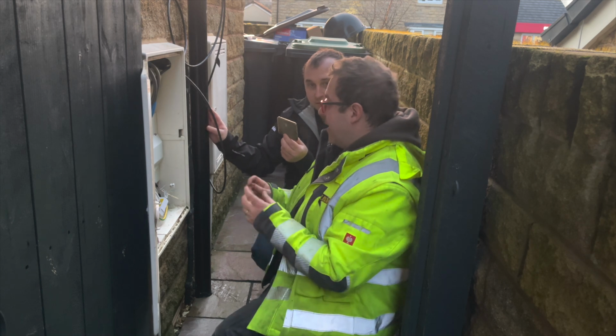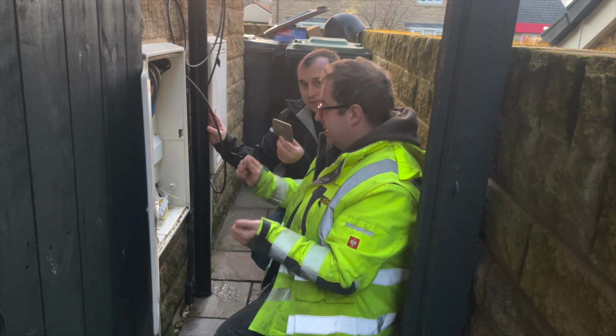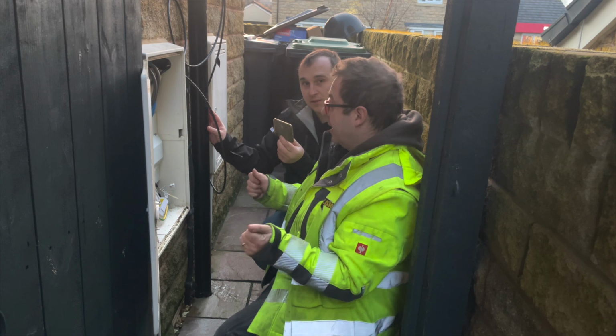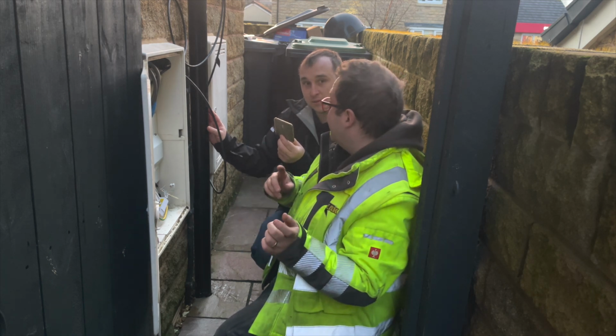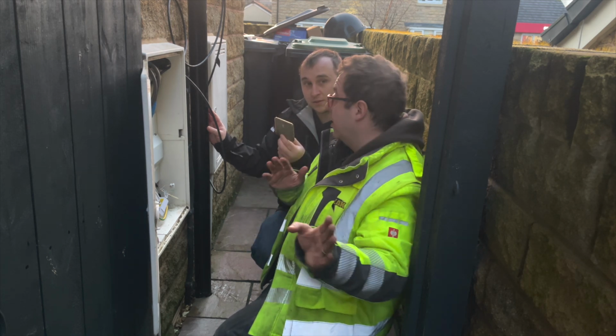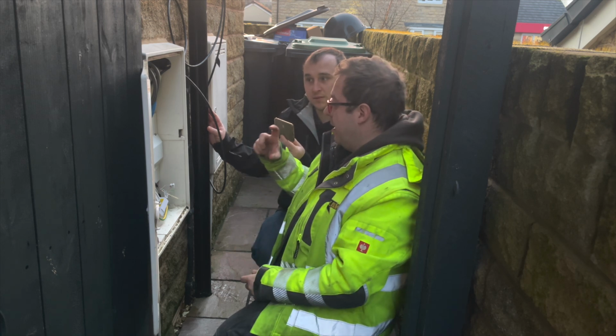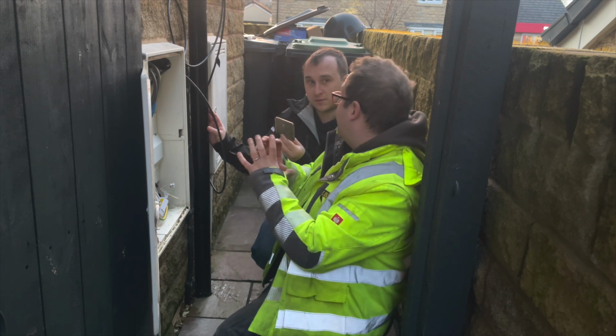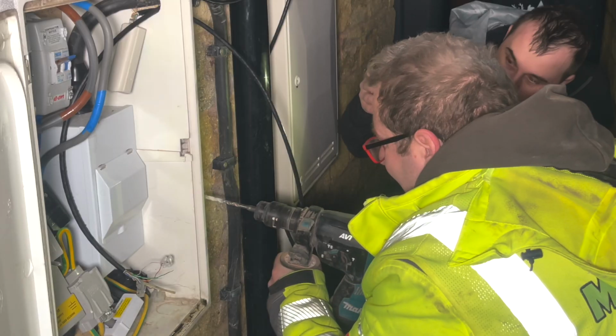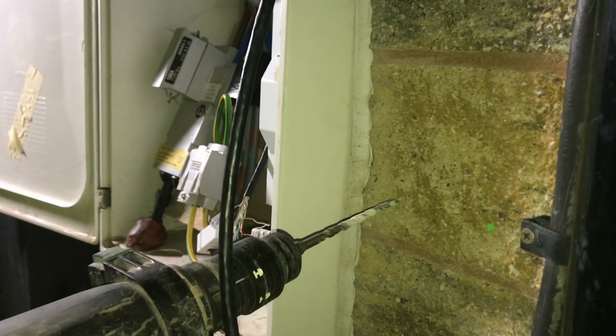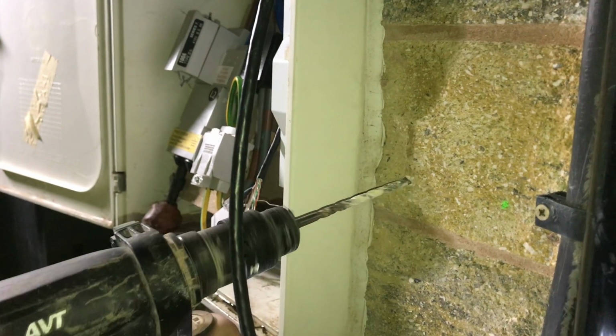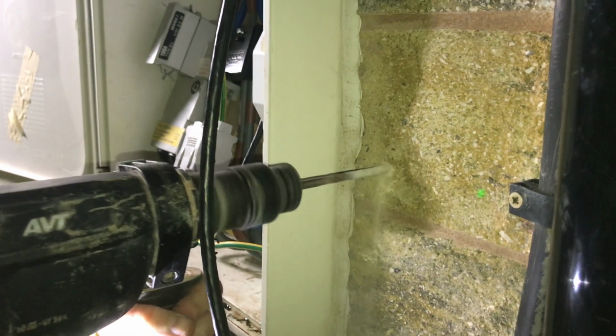Some of them have hardwired CTs which are on a single string, but if you want to go over a longer length of cable like this one over a longer distance, then they have a meter, which is a DIN rail mounted meter. And the enclosure, since we're doing it outside this DNO box, we're going to use a waterproof, IP rated enclosure.